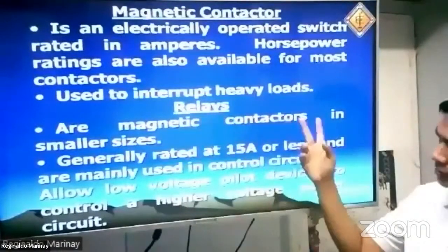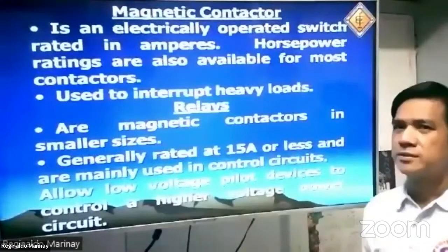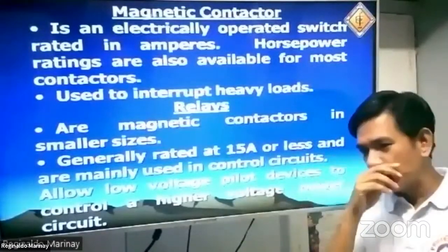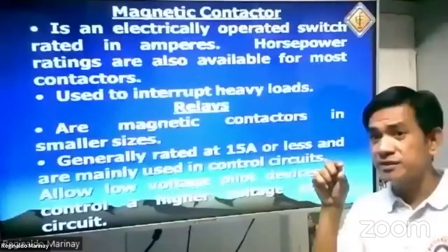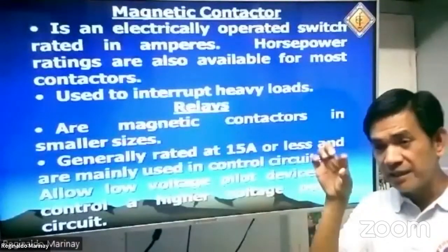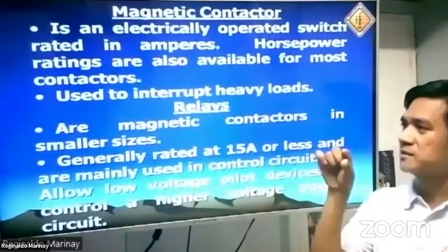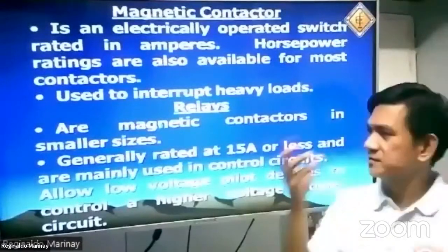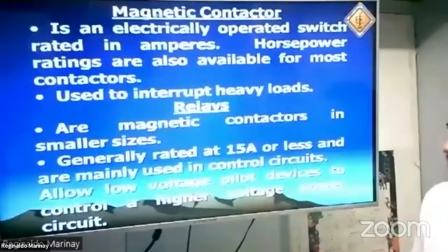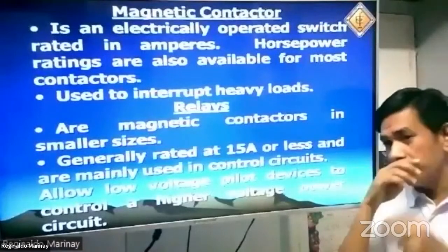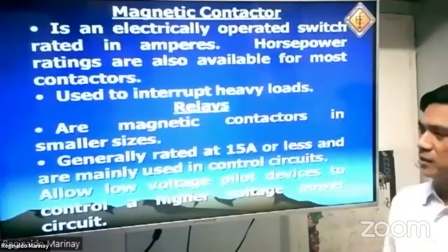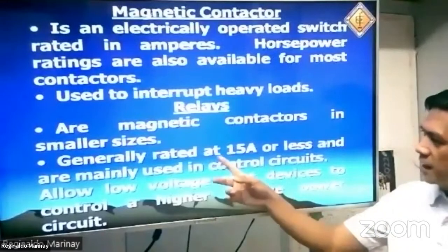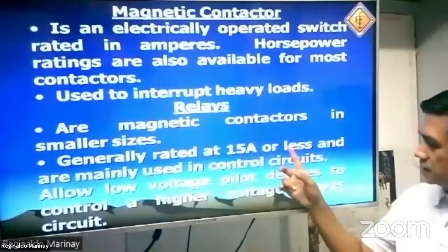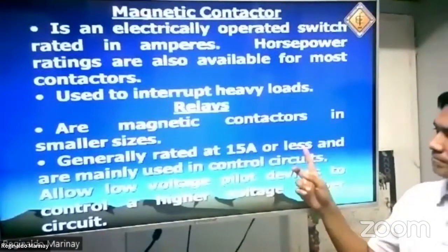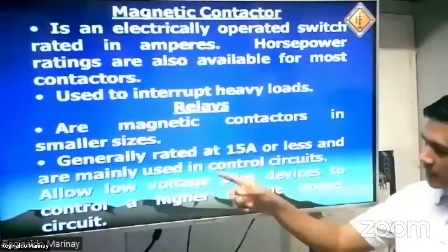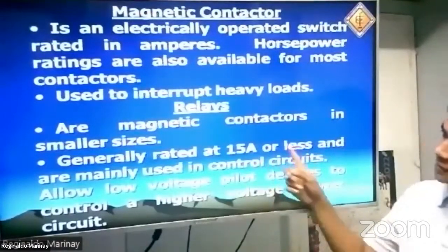Relays are magnetic contactors in smaller sizes, so they term it relay. In an electronic circuit, you will see a small relay with small contacts simply being called a relay, and then a larger relay is what we call the magnetic contactor. Generally these relays are rated at 15 amperes or less, and are mainly used in control circuits.